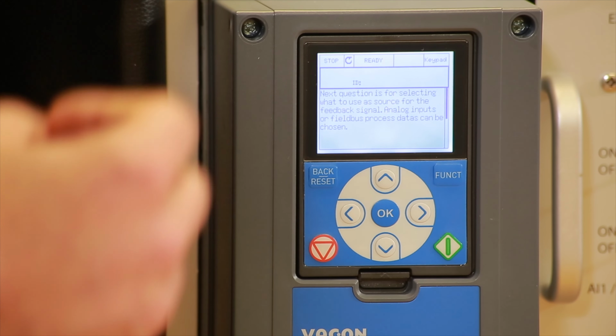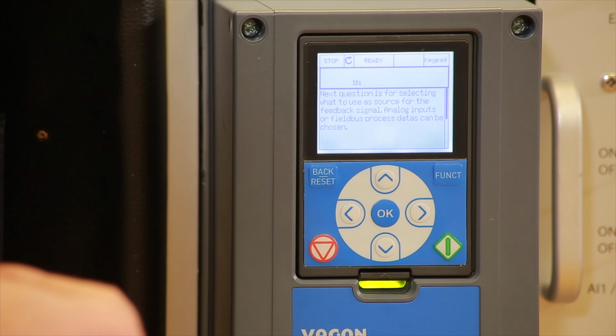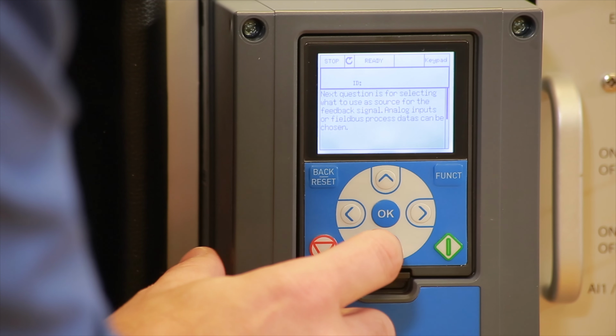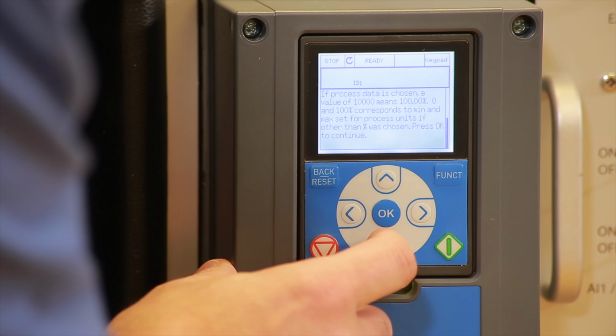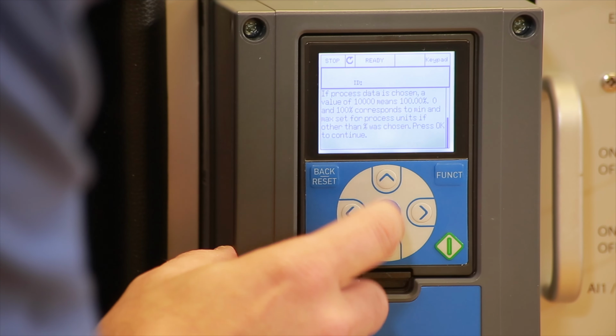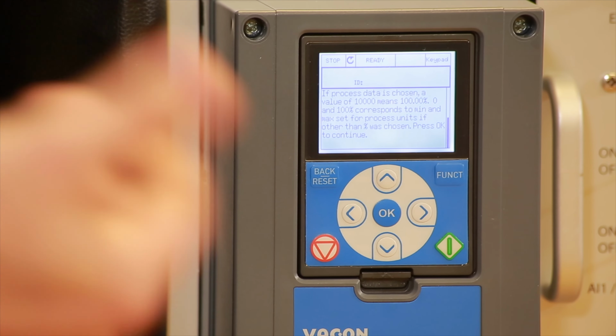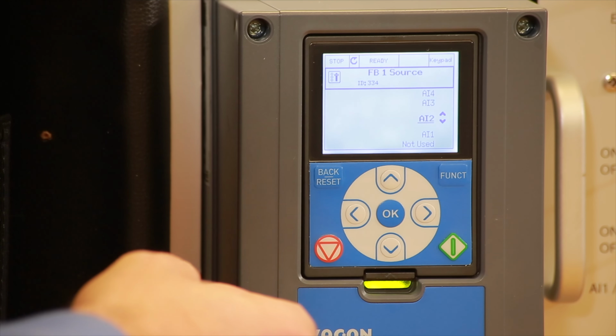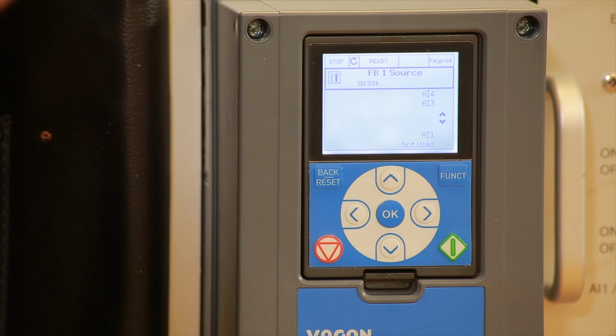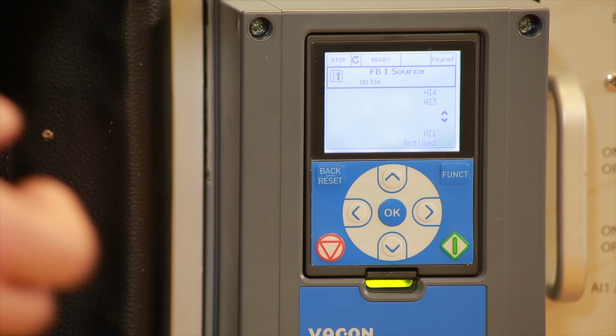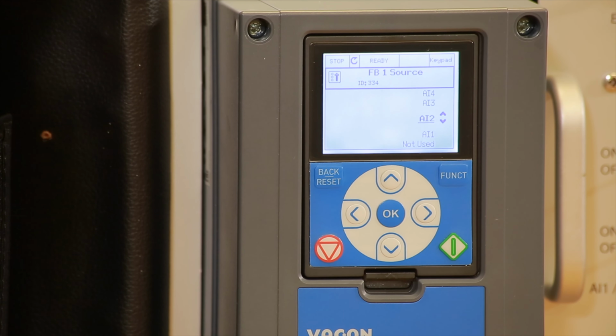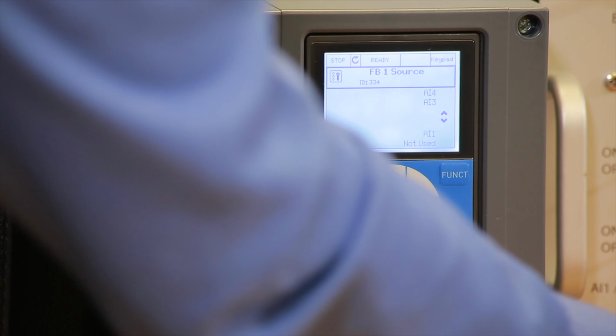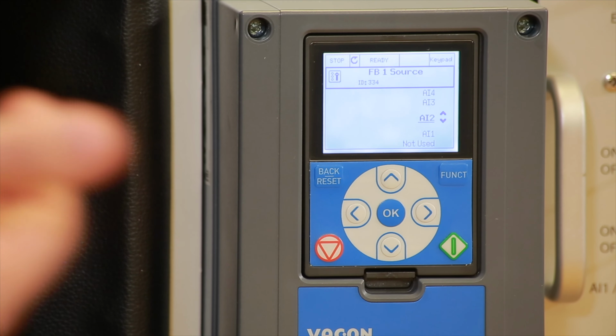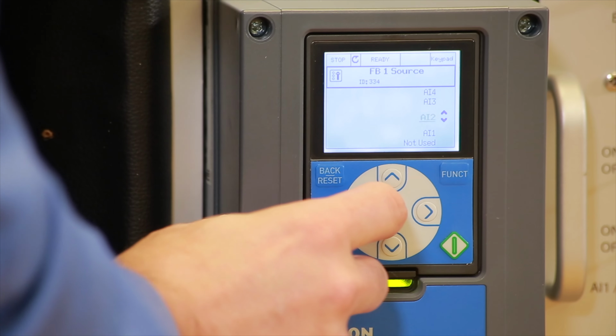Next, the drive says the next question is for selecting what to use as a source for feedback signal. Analog inputs or fieldbus process data can be chosen. If process data is chosen, a value of 10,000 means 100%. In our case, we're going to set PSI, so it makes things very, very easy for us. Now, analog input 1, 2, 3, or 4, the drive gives us an option of where we want to connect the pressure transducer. So we know that the pressure transducer is 4 to 20 milliamps. Therefore, we will plug it in AI2, which is analog input 2. That is the default setting, so we'll just leave it alone.